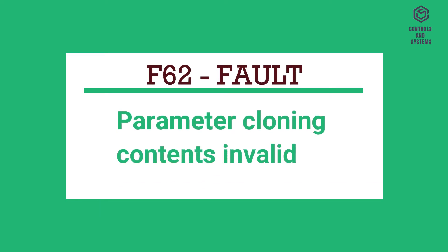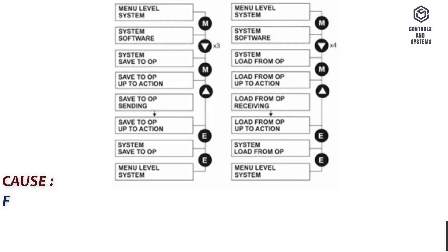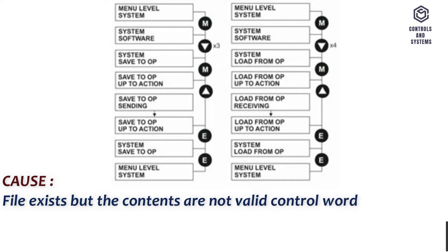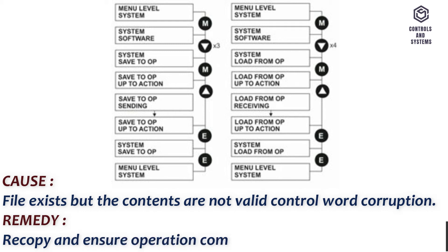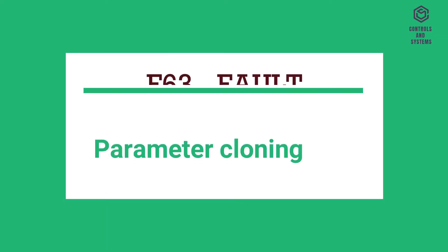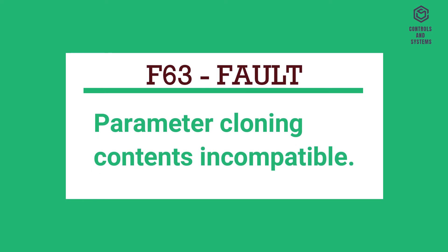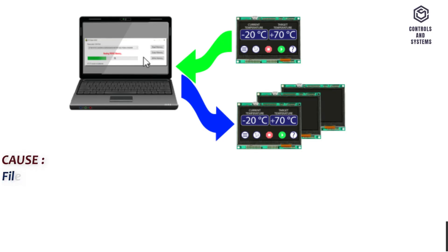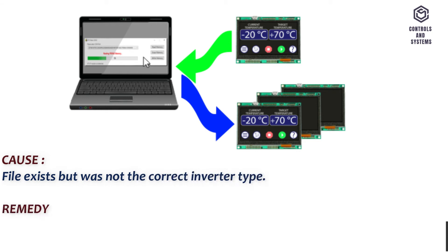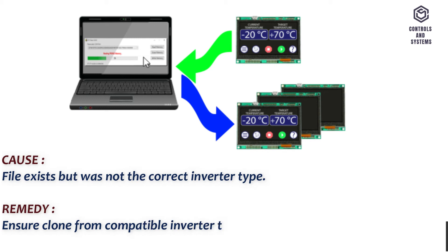F62 Fault: Parameter cloning contents invalid. Cause: File exists but the contents are not valid — control word corruption. Remedy: Recopy and ensure operation completes. F63 Fault: Parameter cloning contents incompatible. Cause: File exists but was not the correct inverter type. Remedy: Ensure clone is from a compatible inverter type.